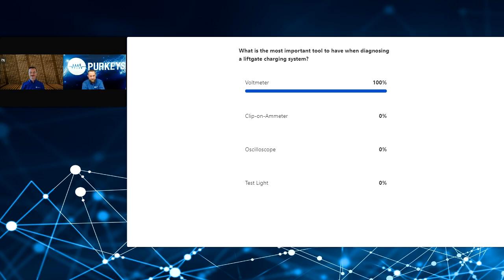100%. Yeah, a voltmeter is really key, and a clip-on ammeter is a bonus, especially with liftgate charging systems. If you've got all these LEDs that are supposed to be telling you what's going on, and something were to happen to an LED, a clip-on ammeter could show without a shadow of a doubt that it's charging because current's flowing. But number one, if you're going to call our tech line to field tech calls, if you're calling Tim or myself, the first thing we're going to ask is, do you have a voltmeter? Because we cannot properly help you diagnose an issue if you don't have a voltmeter. We have all these thresholds built into the system to keep it balanced, so we have to be able to read that voltage.